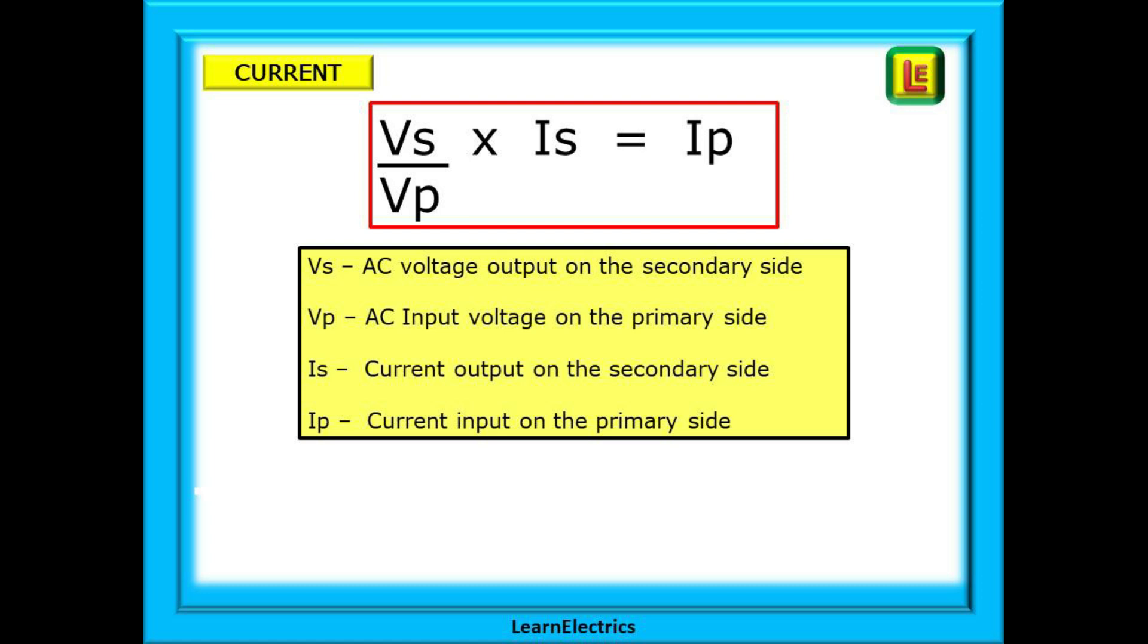Of course, in real life, we wouldn't know the turns ratio, but we should know the primary and secondary voltages, and the current demand in amps of the secondary side. This formula shows us that if we divide the secondary voltage by the primary voltage, and then multiply this by the secondary current, we will find the primary input current of the transformer.